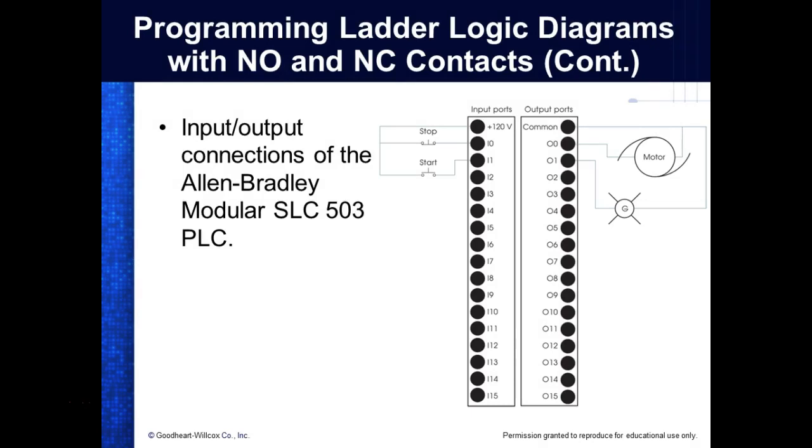You have to use the symbols that we use in motor controls. So this is a symbol of a normally closed push button. This is a symbol for a normally open push button, but it should be spread out. This is a symbol for a light, and this is a symbol for a small motor. I've never seen that symbol before. Can't be a big motor. I think I told y'all most rule of thumb is the output port on most PLCs weighs around 2 amps. So you can't run a motor, but we can use that 2 amps to pull in a relay, right? And that relay can do what? Can run a motor. So every one of these motors over there run through a relay.